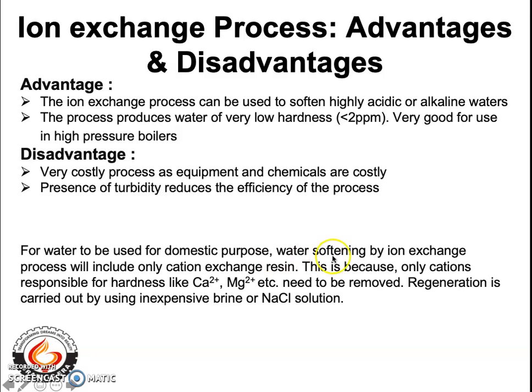For water to be used for domestic purposes, water softening by the ion exchange process will include only the cation exchange resin. This is because only the cations responsible for hardness — that is, calcium and magnesium ions — need to be removed. The anions do not have any specific disadvantage for water used for domestic purposes. The regeneration in this case is carried out using an inexpensive sodium chloride solution. This is all about the ion exchange process.